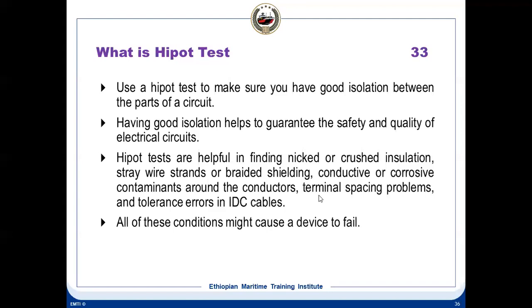Having good isolation helps to guarantee the safety and quality of the electric circuits. Hipot tests are helpful in finding crushed or nicked insulation, stray wire strands or braided shielding, conductive corrosive contaminants around the conductors, terminal spacing problems, and tolerance errors, all of which might cause a device to fail. High potential test means you are applying a high potential across this insulation and confirming that your insulation is good, or the isolation is good.